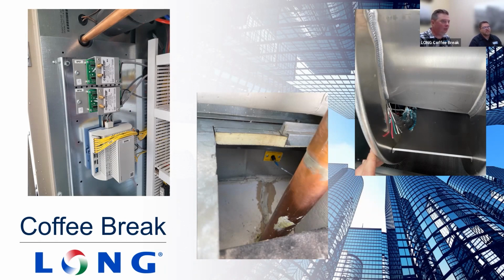The middle picture you see is an example of following the installation instructions. That is the discharge air temp sensor. The discharge air temp sensor on our Rebel units, per the IOM, is supposed to be installed between 5 and 10 feet downstream of the unit before any additional appliances, VAVs, fan powered boxes, or anything like that. In this particular instance, that's the penetration for the water lines for the hydronic heating coil. It is literally mounted in the curb right under the unit. So it's not in the proper location. That'll impact the ability of these units to run and meet the sequence. It'll short cycle off and on heat and not allow it to function properly.